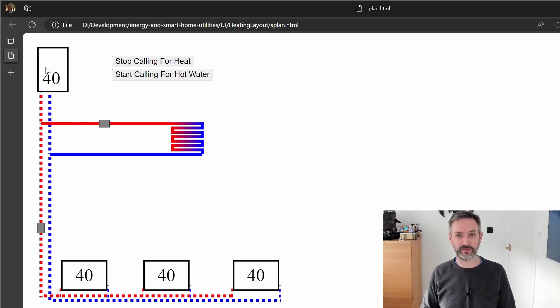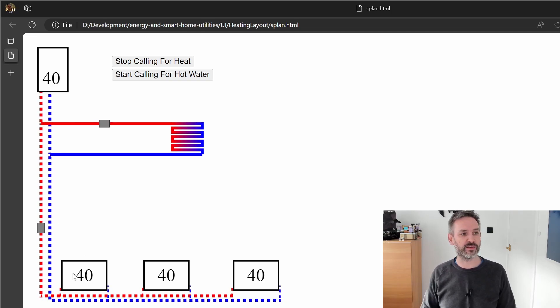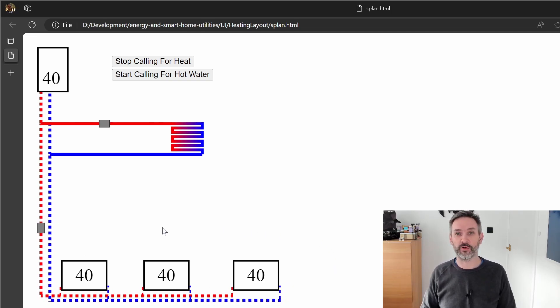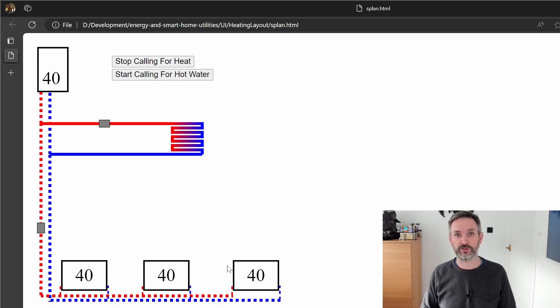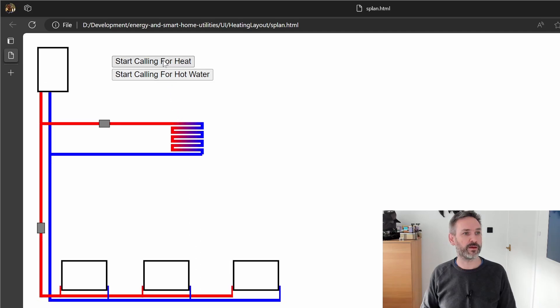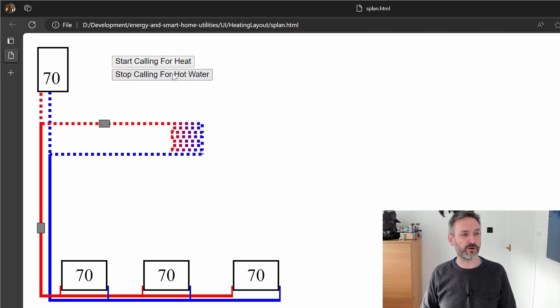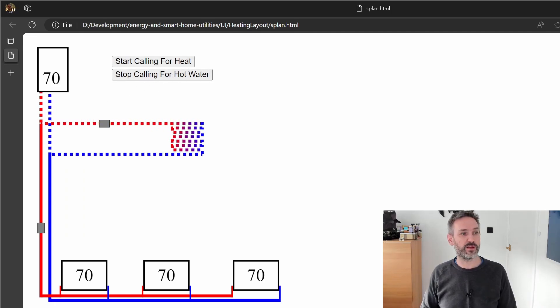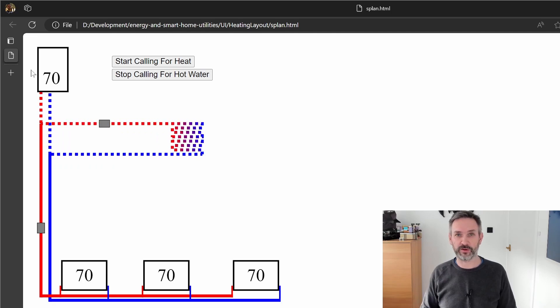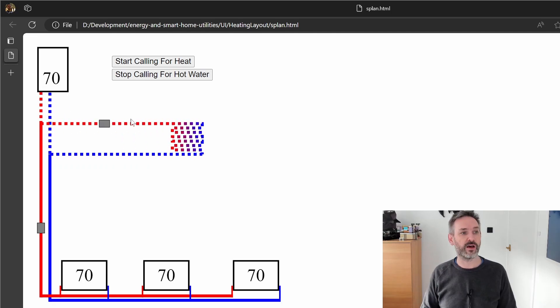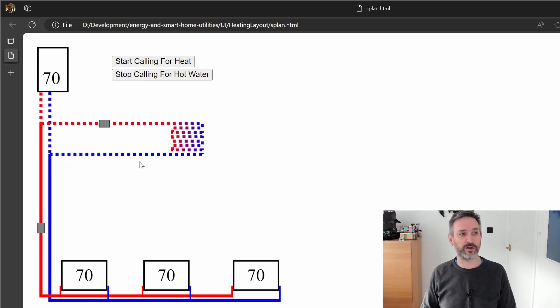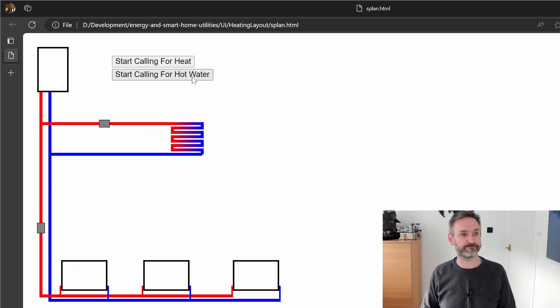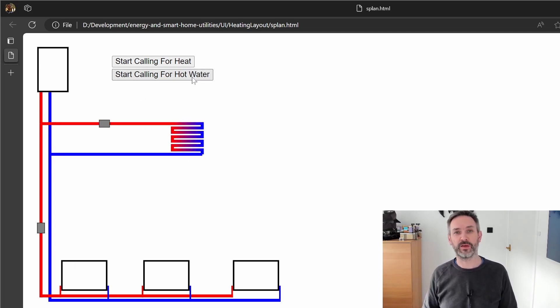So essentially what happens is when the thermostat calls for heat the boiler will open this little zone valve, sets its flow temperature to 40 degrees in my case and that starts circulating the water around the radiators at 40 degrees. If we then need to boost the hot water the boiler will increase its flow temperature to 70 degrees and that water will circulate around the coil and heat the water.